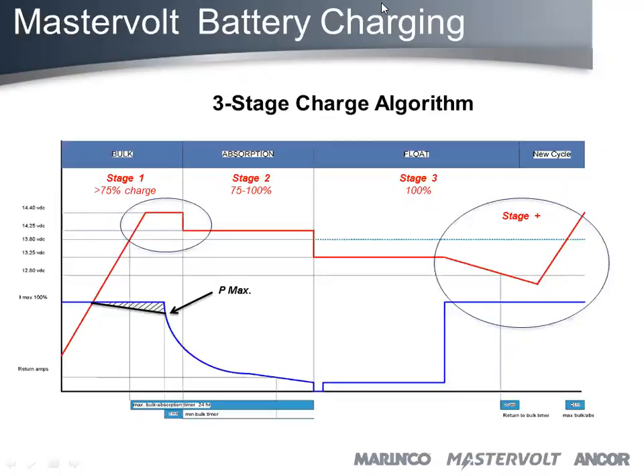That's very tricky, because if you get to this point where it says 13.8, one of those timers kicks in — what we call an absorption timer — and from that point you only have 8 hours to finish your charge cycle. If it doesn't finish in those 8 hours, it automatically pushes itself into float.